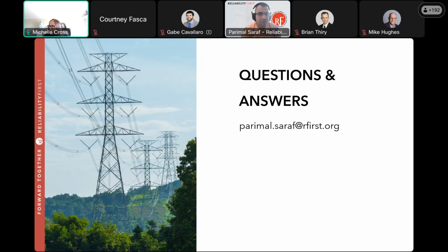Moving on to the next question. Now, this question I think came in when you were talking about the NERC alert recommendations. The question is, why is it not recommended to use user-defined models for interconnection-wide studies and only for local area studies? That's a great question again. So user-defined models, as I said, are black boxed. And a lot of times what these black box models mean is that you essentially receive something called a DLL, which is a dynamic link library.